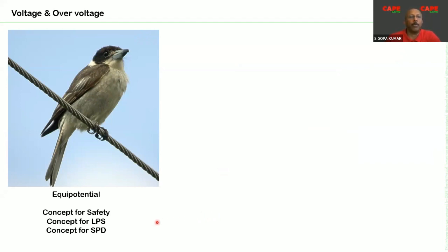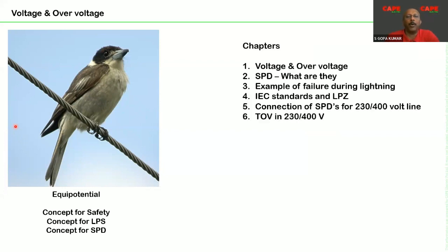Now, coming back to the concept, it is nothing but equipotentialization, not only for electrical safety. The concept for the lightning protection system, the concept for SPDs, everything is based on equipotential bonding or equipotentialization. How well you make the equipotentialization finally decides whether your electrical installation is safe against touch voltages, safe against lightning, safe against surges, and so on.